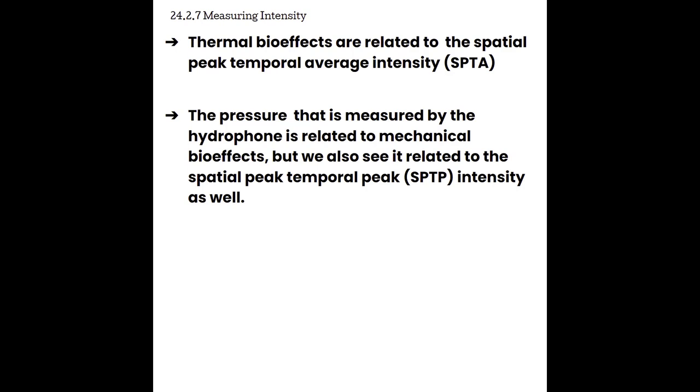For bio effects, we know that thermal bio effects are related to the spatial peak temporal average intensity or the SPTA. And we'll see that by measuring the pressure with the hydrophone, we can understand a little bit more about the mechanical bio effects. But we also know that mechanical bio effects are related to the spatial peak temporal peak or the SPTP intensity.